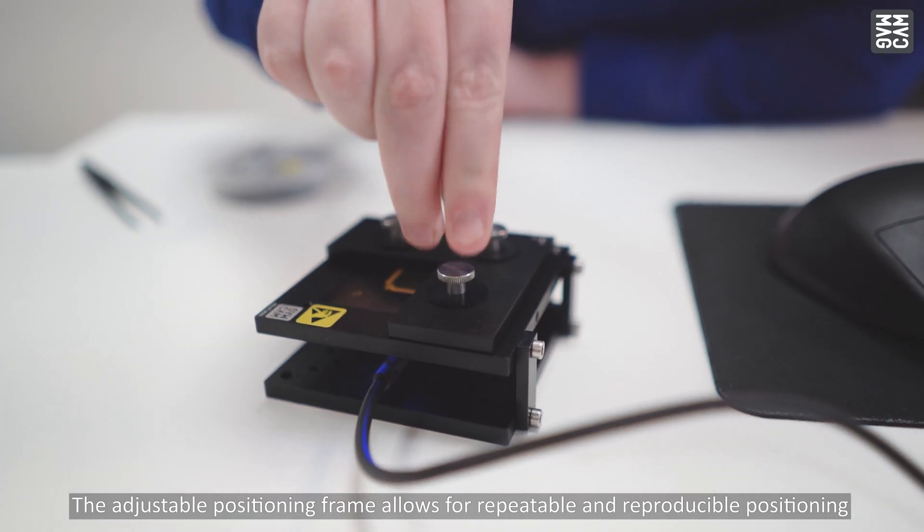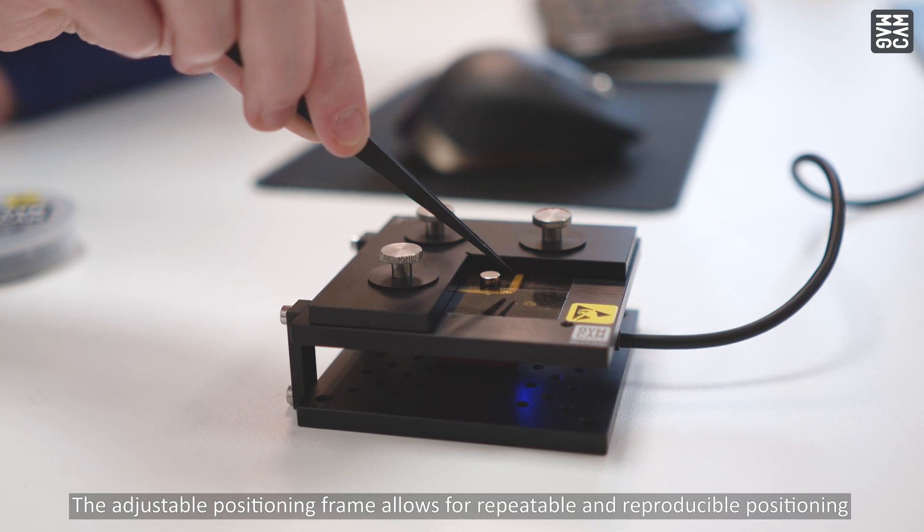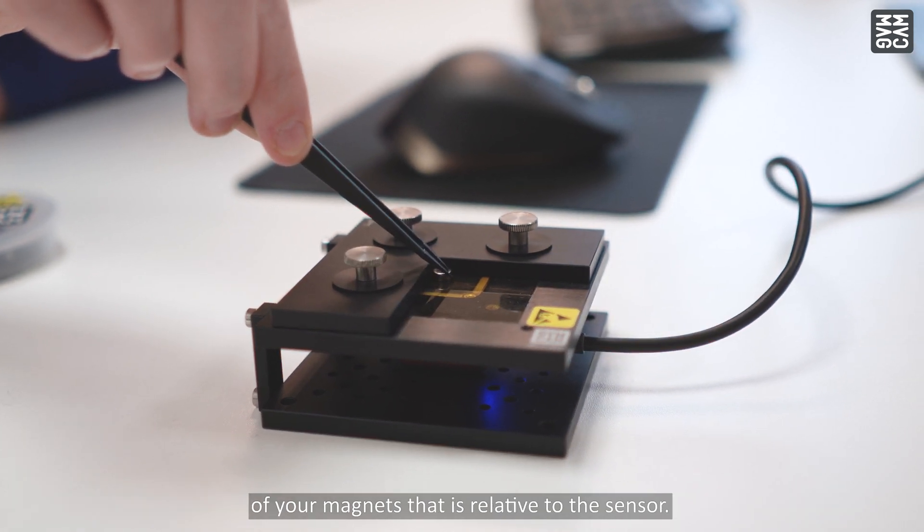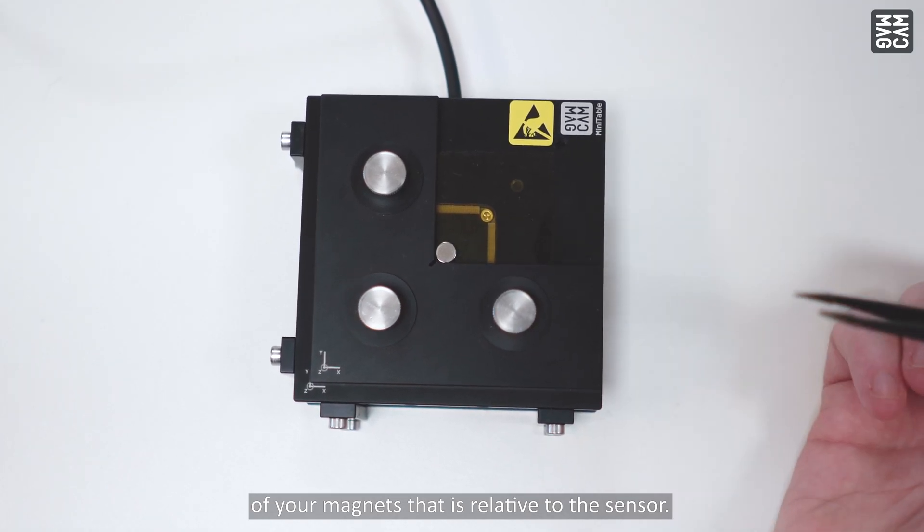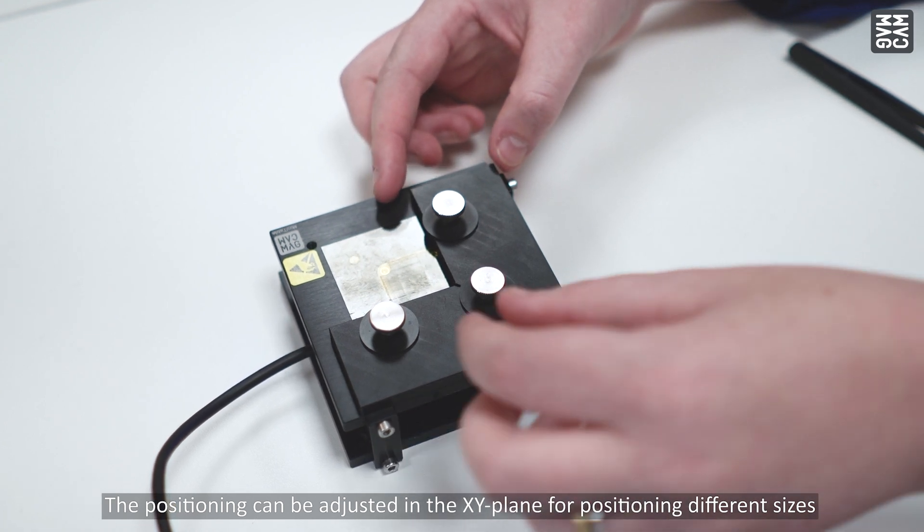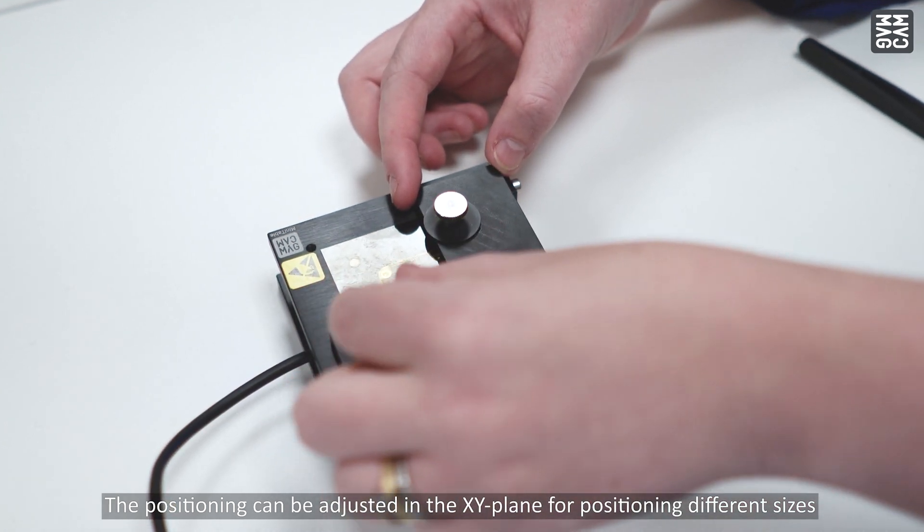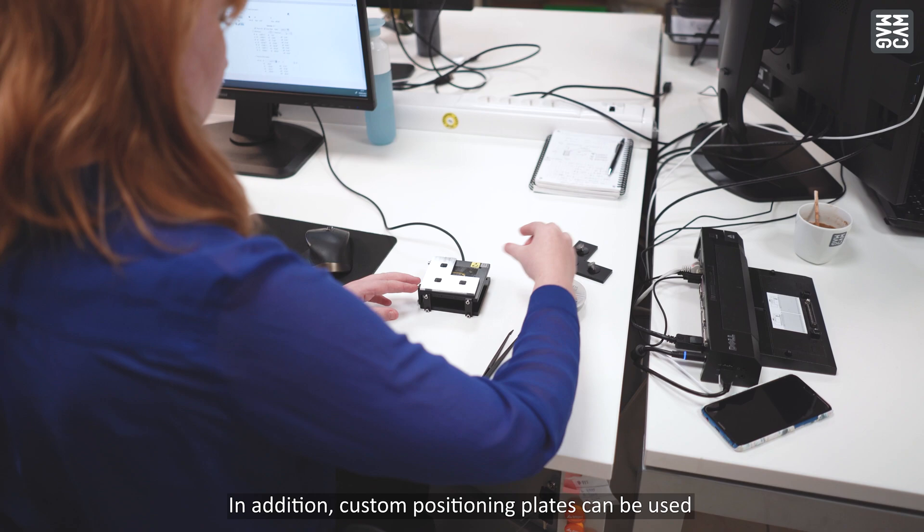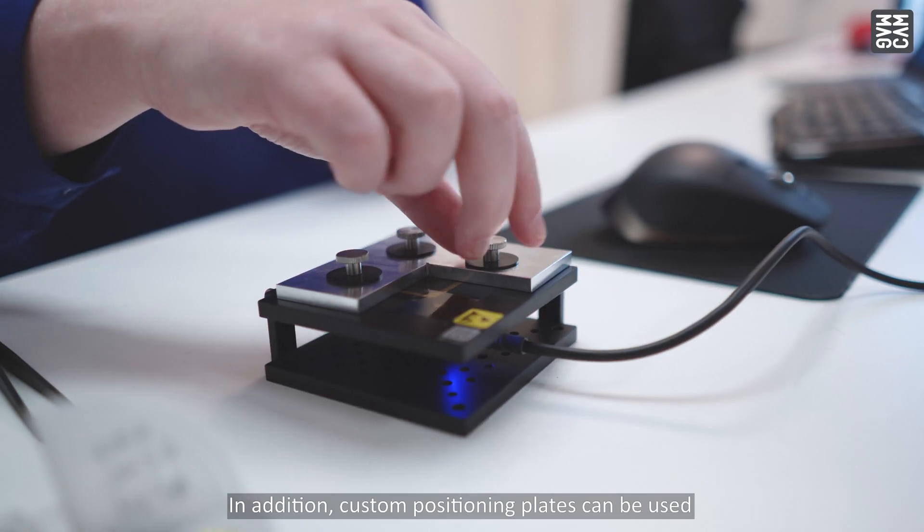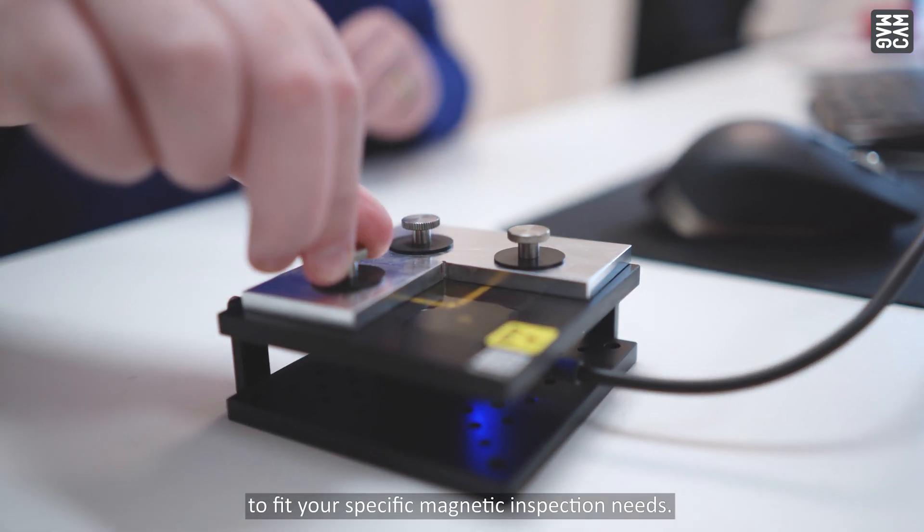The adjustable positioning frame allows for repeatable and reproducible positioning of your magnets relative to the sensor. The positioning can be adjusted in the XY plane for positioning different sizes. In addition, custom positioning plates can be used to fit your specific magnetic inspection needs.